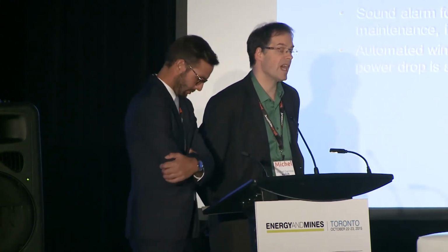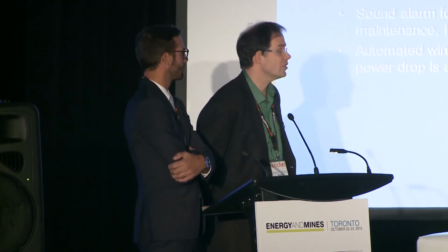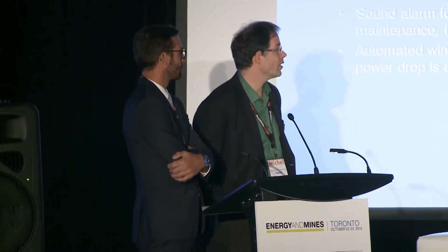Wind turbine icing is being calculated in real time, so we have predictions on when icing accumulation is going to go above a certain limit and the wind turbine stops, and we can warn the operators with a sound alarm that tells them to watch out. We've got automated wind curtailment when it's needed, which allows the operator to go off the screens and do some maintenance, knowing that the automatic mode will guarantee the grid stability. We've got automated emails for alarms that are sent and dispatched to the south, so we are on a 24-hour alert if anything is happening. We don't want to lose wind power. So those are very sensitive for the operator.